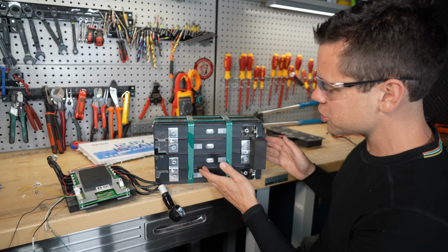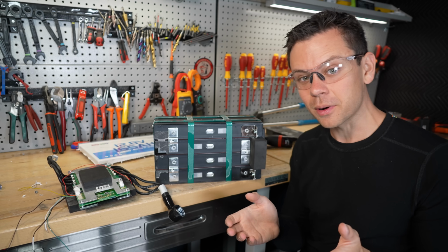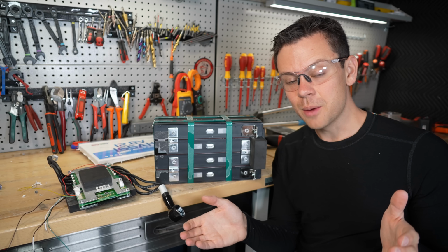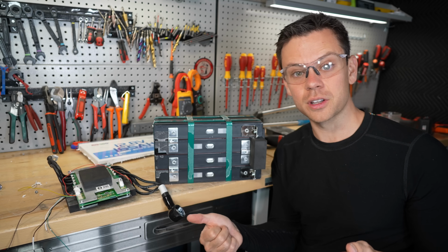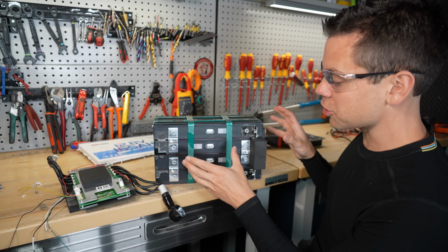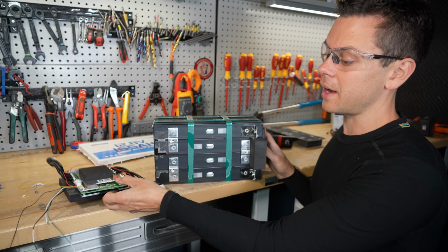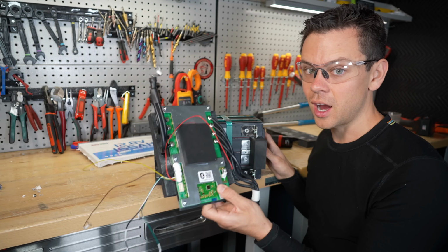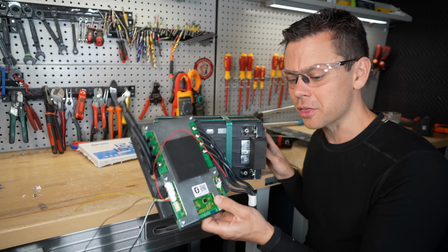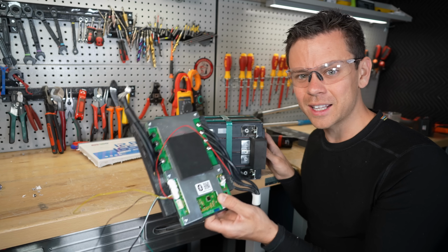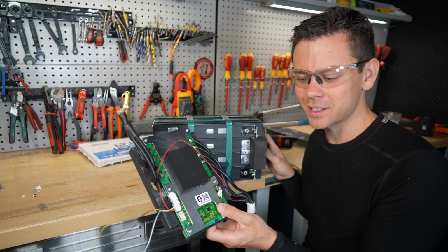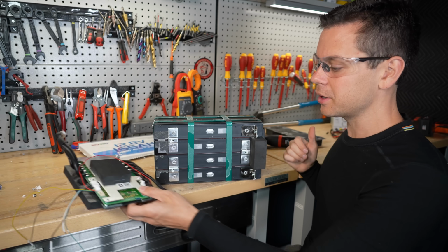Now that these are so cheap, it's better off, it's actually cheaper to buy larger batteries, because then you can use less copper to hook them up to your system. But with a larger battery we need a larger current capacity BMS, so you have to be mindful of that. Sometimes there will be a 300 amp hour battery and it can only output 100 amps. So be sure to check when you buy these budget batteries.